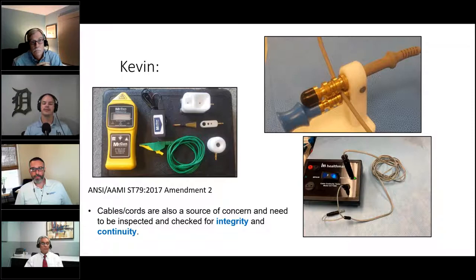The new ANSI AAMI ST79 amendment states that cables and cords need to be inspected for integrity and continuity. So what does that mean? You see that same insulation tester to the left of the screen, and we can use the accessory on the upper right to test the insulation of monopolar and bipolar cautery cords. This ensures the cord is free of defects in the insulation, so the electricity stays within the cord safely as intended, should you adopt this practice and test all your cords.